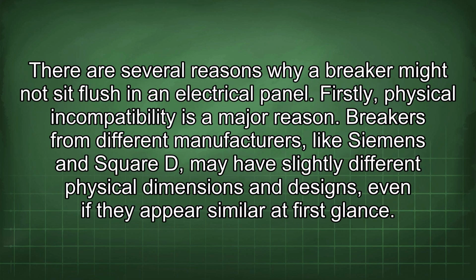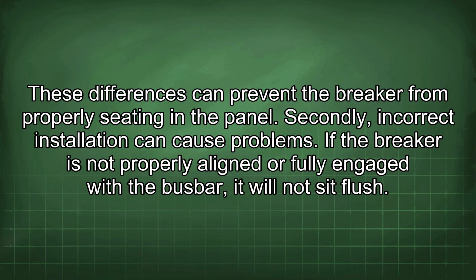There are several reasons why a breaker might not sit flush in an electrical panel. Firstly, physical incompatibility is a major reason. Breakers from different manufacturers, like Siemens and Square D, may have slightly different physical dimensions and designs, even if they appear similar at first glance. These differences can prevent the breaker from properly seating in the panel.